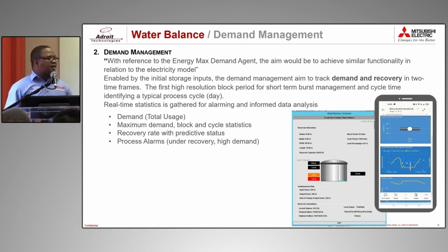And it helps us to do demand management in the sense that we know the time periods in which we consume the most water. So it brings us a solution in that we will be able to plan our pumping cycles. Now we can choose the times where electricity is least expensive, and we can pump during those time periods. So the statistics which come in this agent are things like the demand, the maximum demand, recovery rates, and process alarms.